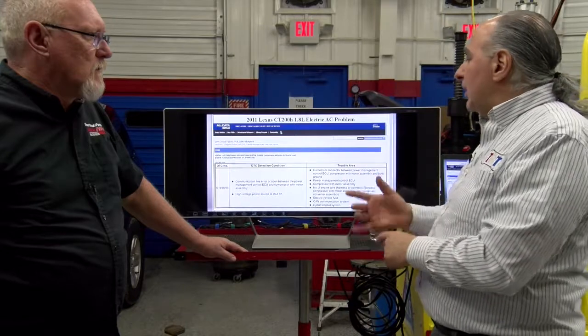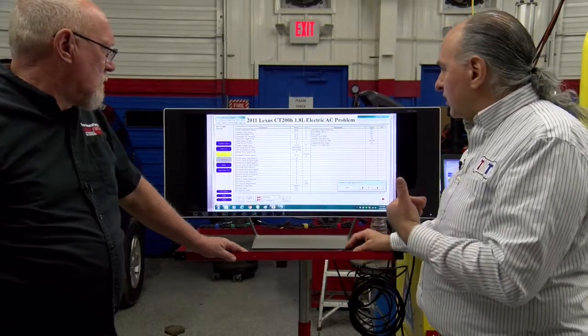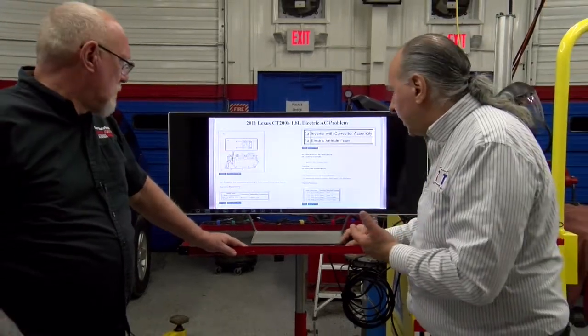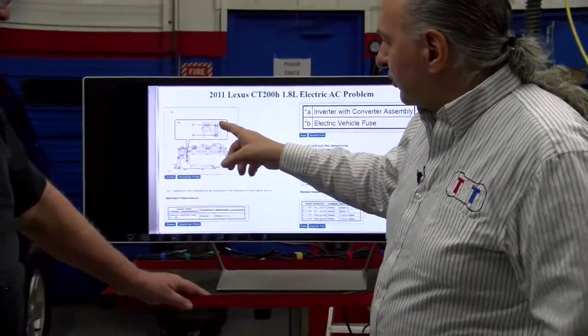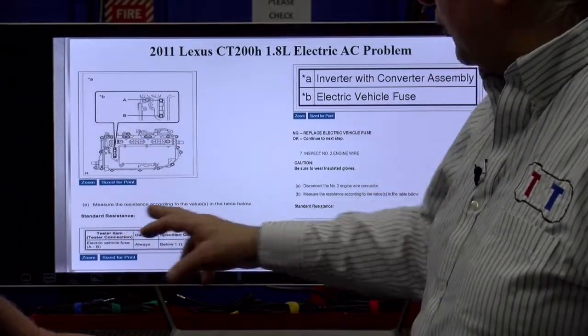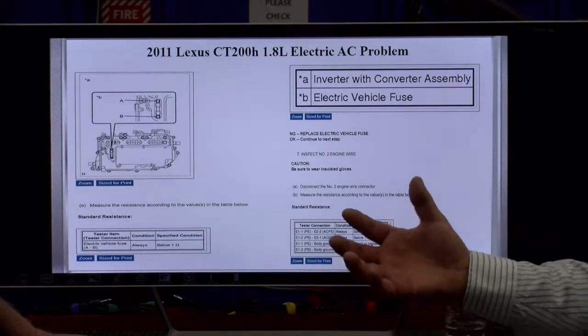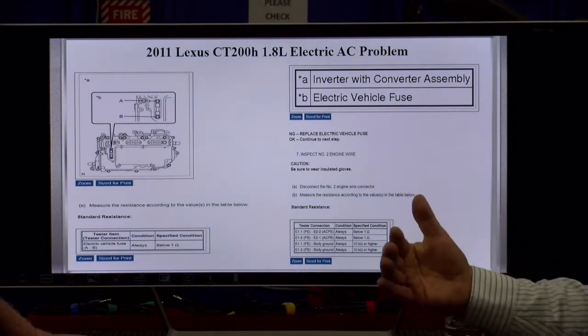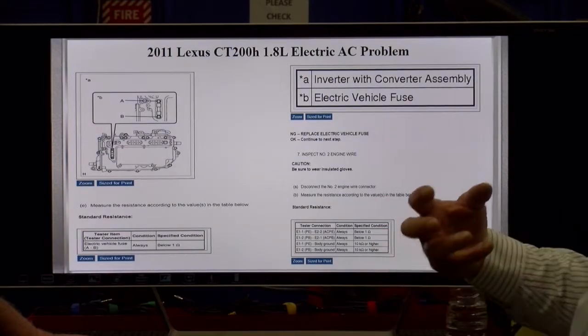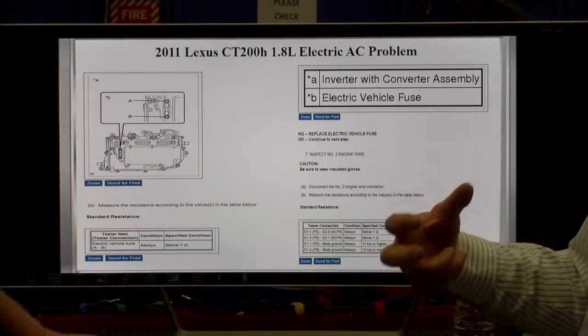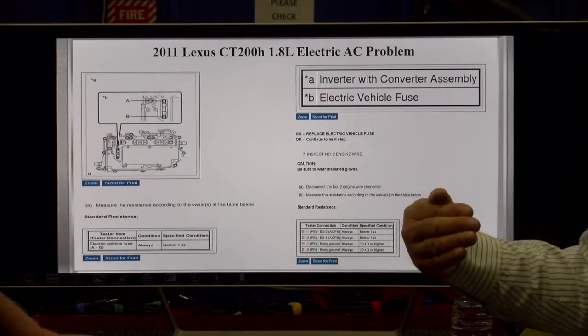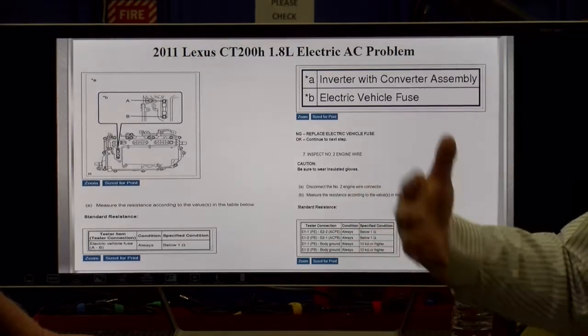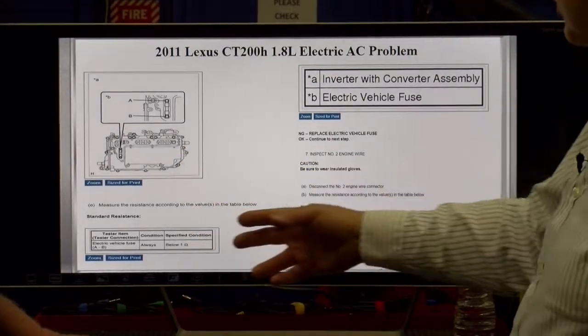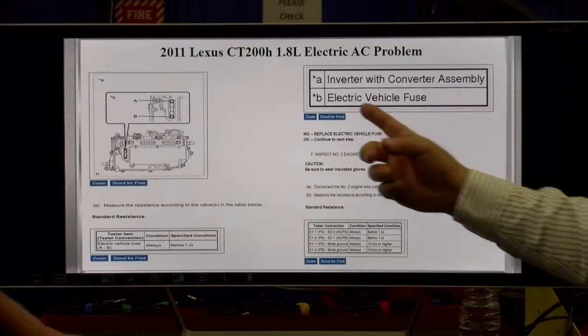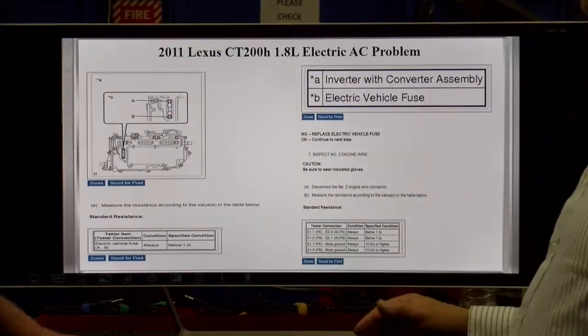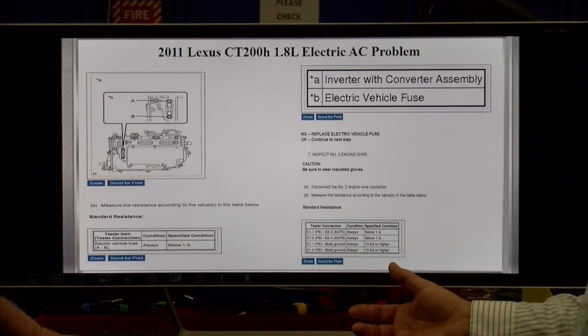Is either a fuse connector in the computer or in the inverter setup, or, and I don't think I have a picture of that. Oh, yes I do. We'll go back to this here. So you see this? This is the inverter cover off, and it tells you can measure resistance. Well, the meg ohm meter does resistance, but there's nothing like a real good voltage test. Because the whole idea of a meg ohm meter is to pressurize it, like we would pressurize a pipe. Voltage is pressure, right? Current is flow. We would want to see, if we pressurize it, does it hold or is it leaking somewhere? So we would do both. We would follow their procedure. Notice it says inverter assembly or electric fuse. Maybe that blew. Maybe it was weak.